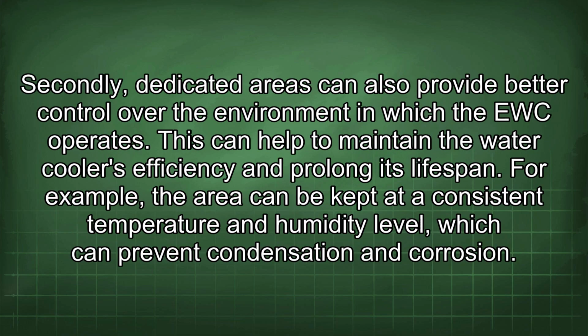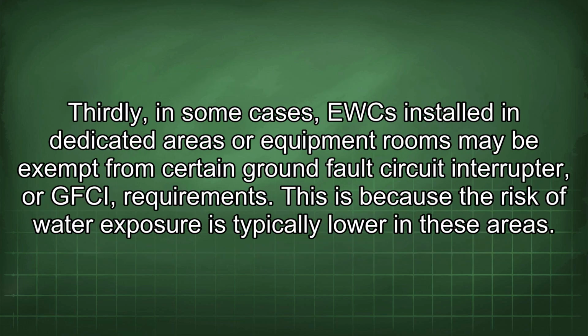Secondly, dedicated areas can also provide better control over the environment in which the EWC operates. This can help to maintain the water cooler's efficiency and prolong its lifespan. For example, the area can be kept at a consistent temperature and humidity level, which can prevent condensation and corrosion. Thirdly, in some cases, EWCs installed in dedicated areas or equipment rooms may be exempt from certain ground fault circuit interrupter or GFCI requirements. This is because the risk of water exposure is typically lower in these areas.